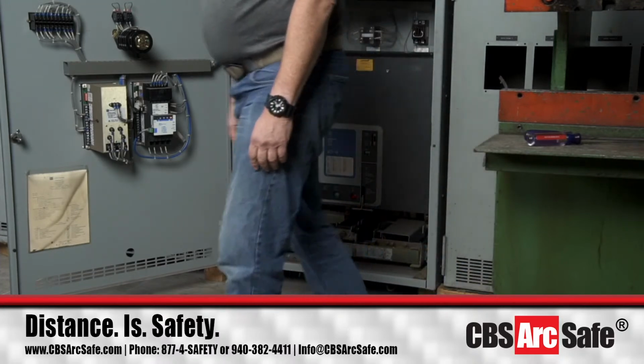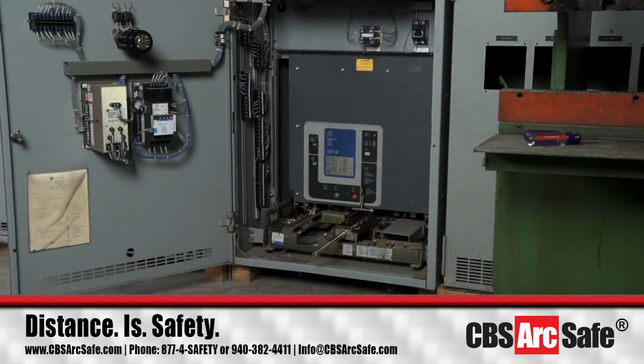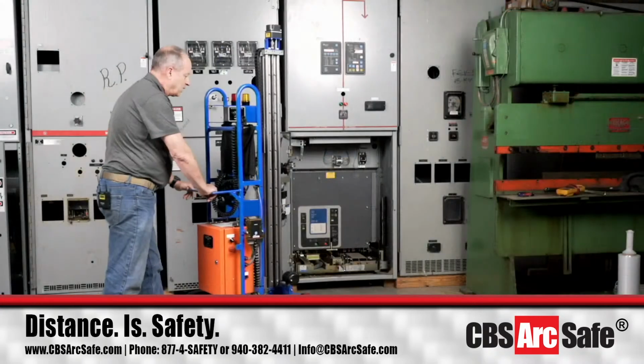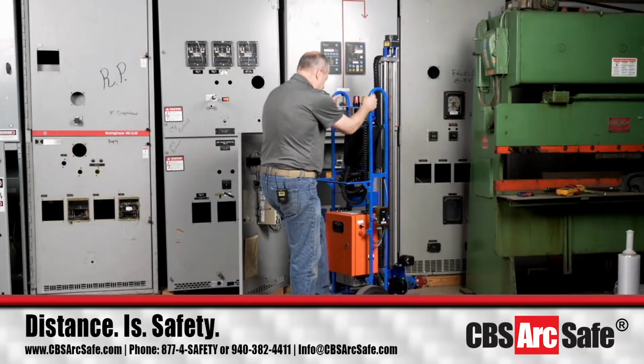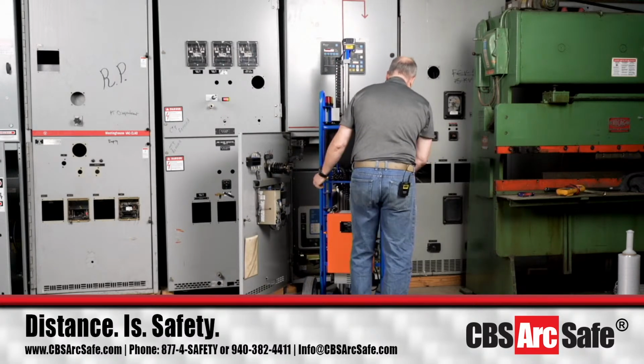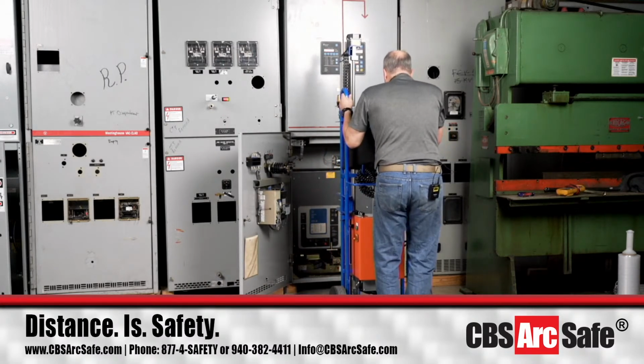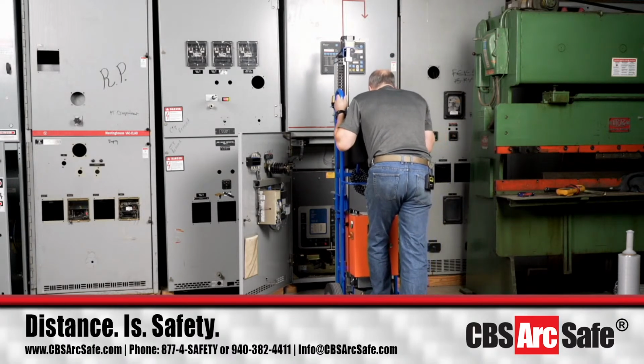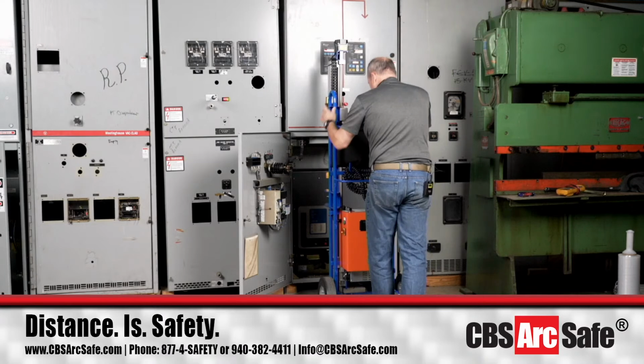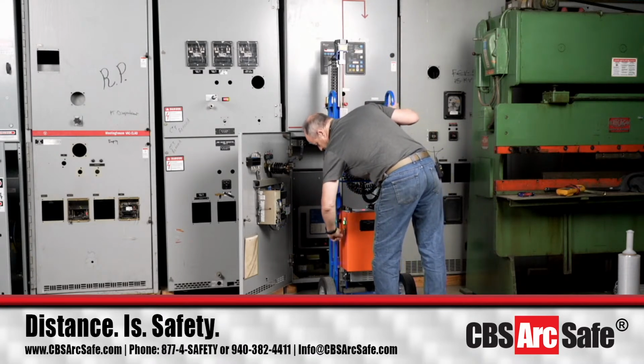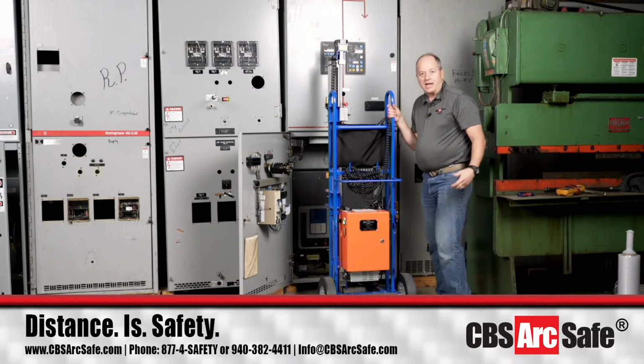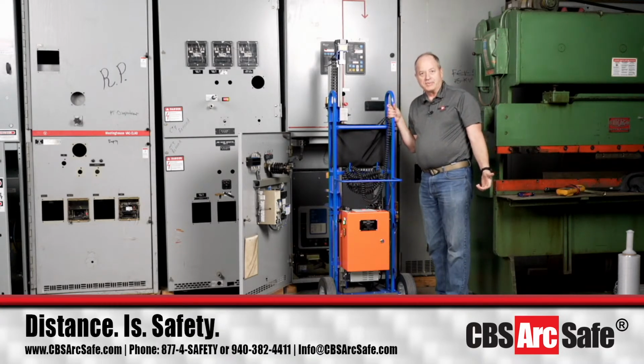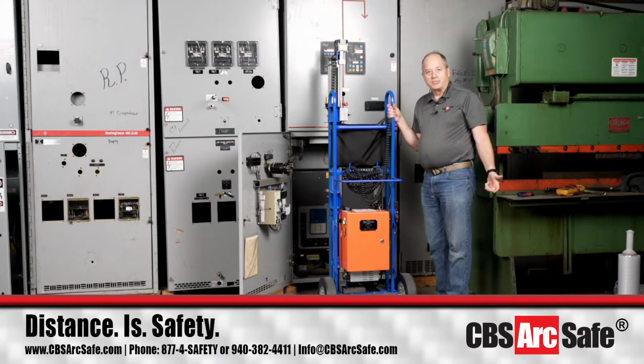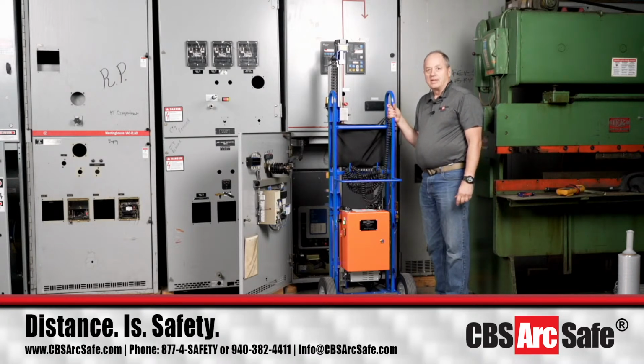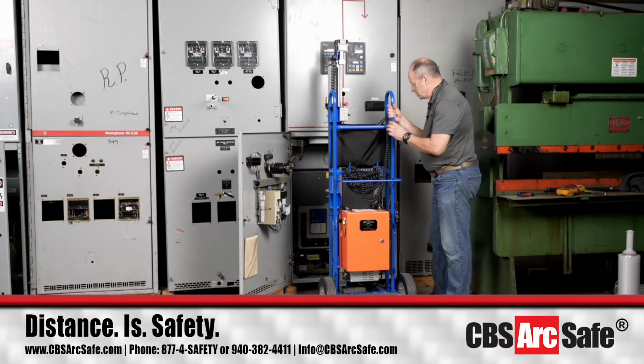Now, one of the other things you need to know is this. The RRS-1 spins at a speed comparable to a man. That's important because if you try and rack a breaker faster than what a man does, you can actually tear up the breaker and the racking mechanism. So we've worked to make sure that our speeds are close to what we can do as a human being. I was a human guinea pig, along with a couple of other people, where we would literally get down and rack the breakers on our hands and knees with somebody timing us, and we would compare our speed to the RRS-1. And we played with different motor speeds to get us in the right speed range for this.